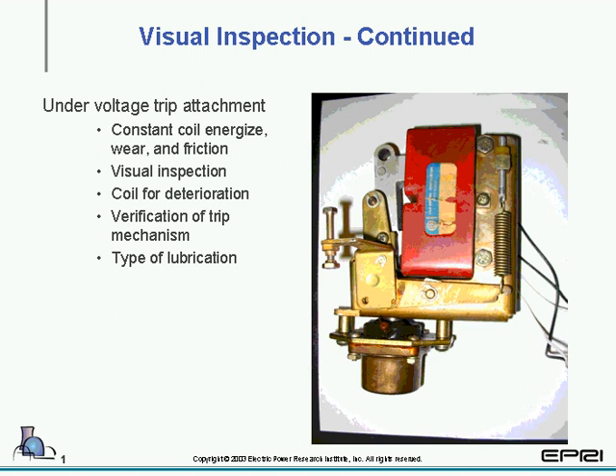Undervoltage trip attachments, along with visual inspection and the other list, need to be tested to verify that they're good, and if it has some sort of time delay, which is shown in this particular slide, you're actually going to see a small unit that provides the time delay. It needs to be verified it's within the correct band.